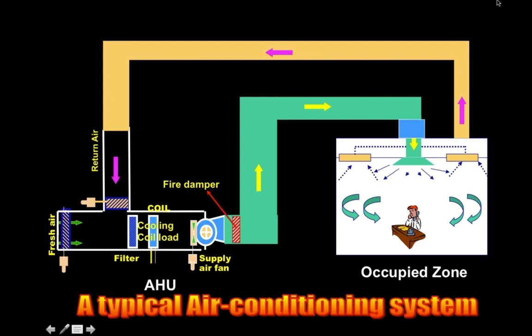I start off with a typical air conditioning system that we have in the tropics, and I'm sure it's probably not very different to climates in London and elsewhere, at least for your summer air conditioning design. We're talking about a room as an example here, but this could be a complete floor or the entire building if it's not too large a building. Then we've got an air handling unit that's going to push the air through a system of ductwork, and then we've got the return air coming back to the air handling unit. And what I would want to highlight here is in the tropical design, we recirculate a good 90% or thereabouts in terms of the return air back into the system.